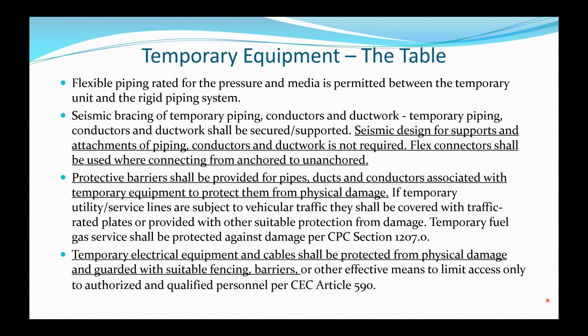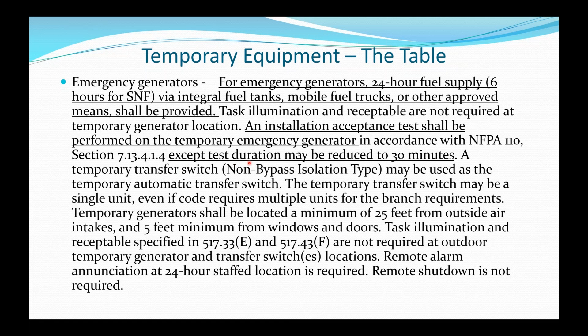For emergency generators, there's a longer section here, so I'm not going to go through it all. The emergency generators must have a 24-hour fuel supply, and have the integral fuel tanks, okay, or mobile fuel trucks or other approved means shall be provided. The installation acceptance test shall be performed on temporary emergency generators per the NFPA, but the difference is that the test duration may be reduced to 30 minutes.